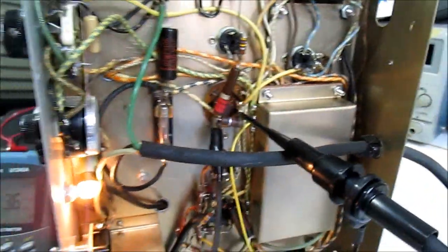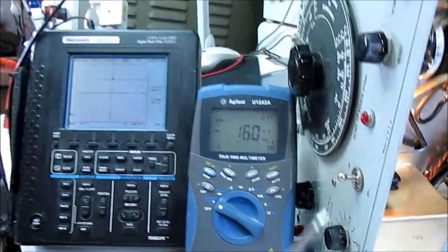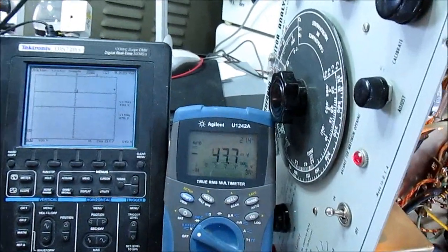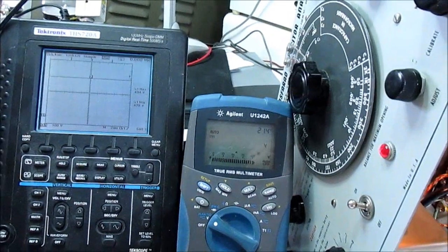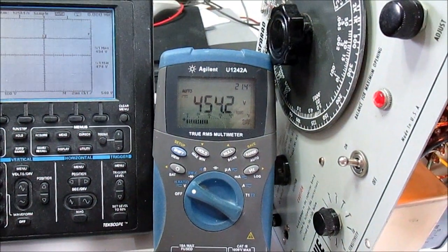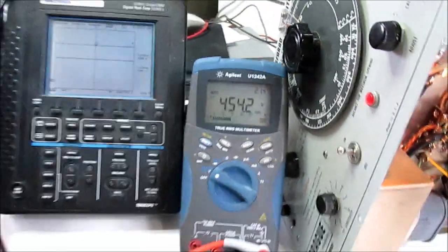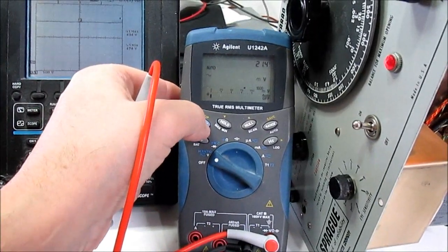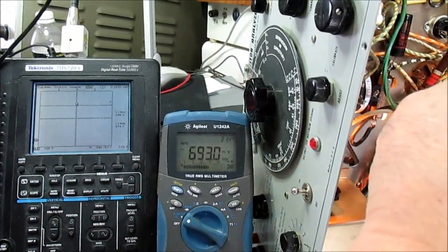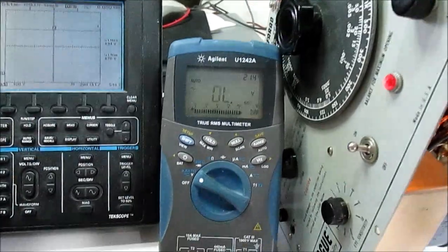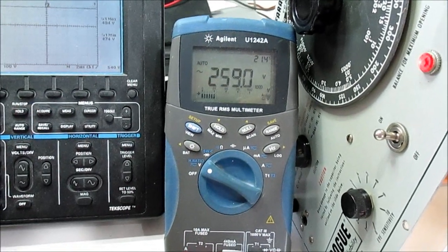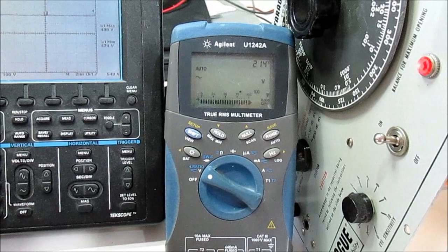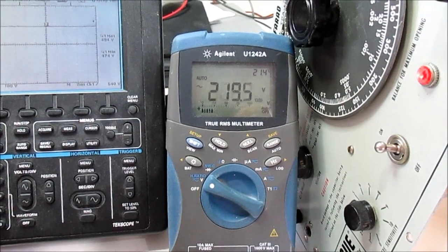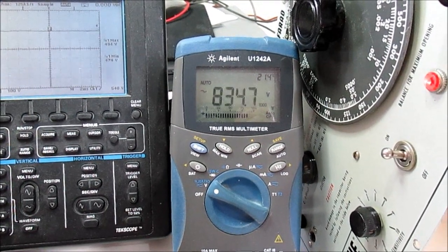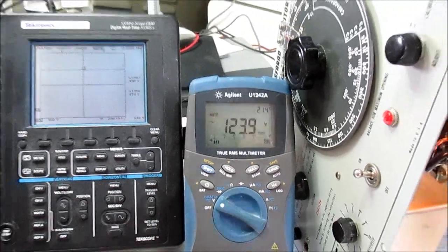As you recall, if I take this and I touch it to that point there, it says 454 volts DC. Fine. If I change this to AC mode and probe over here, it's jumping all kinds of crazy high voltage numbers up and down, over 1,000 volts. And that's the reason why I wanted to get this scope probe on here, to see what we can see.